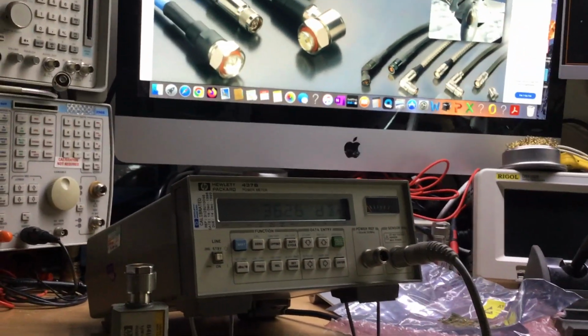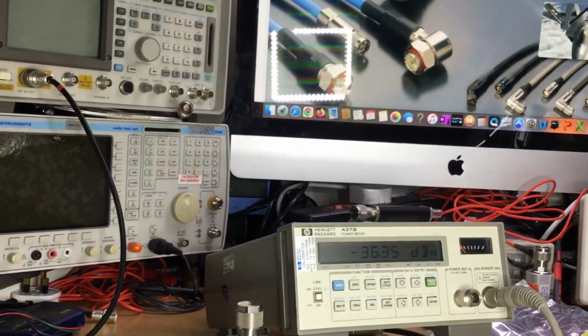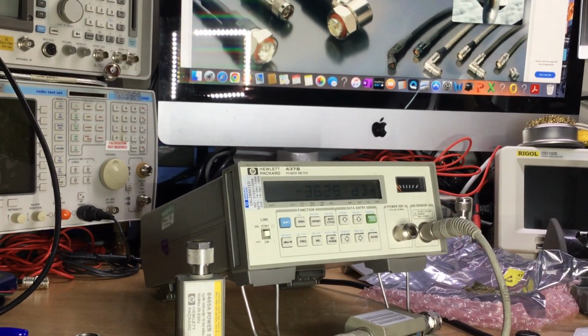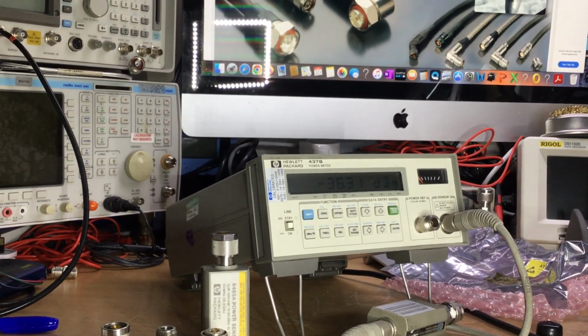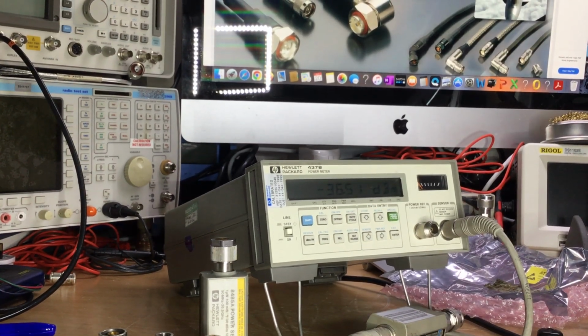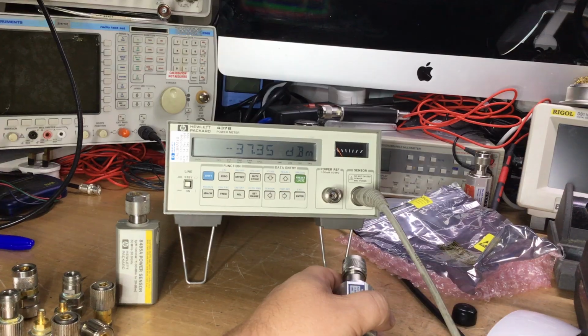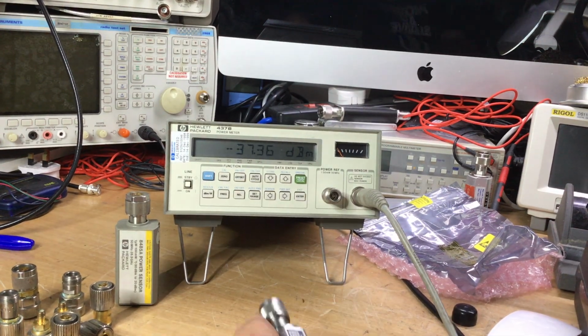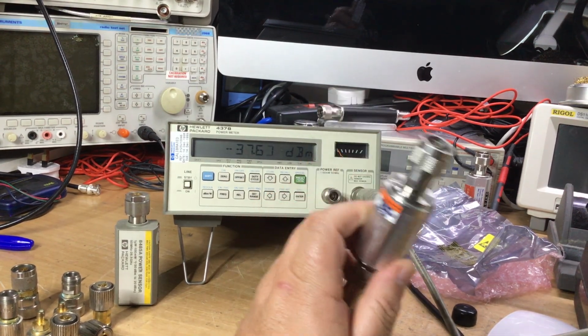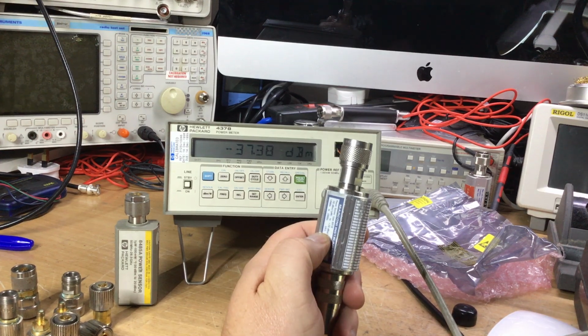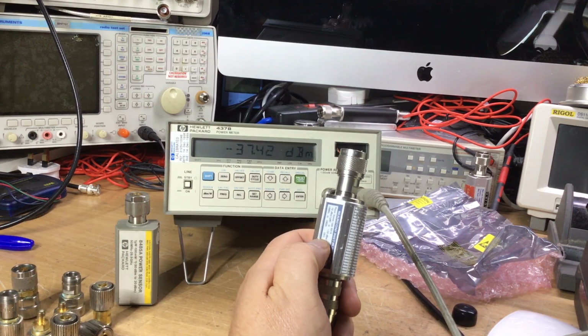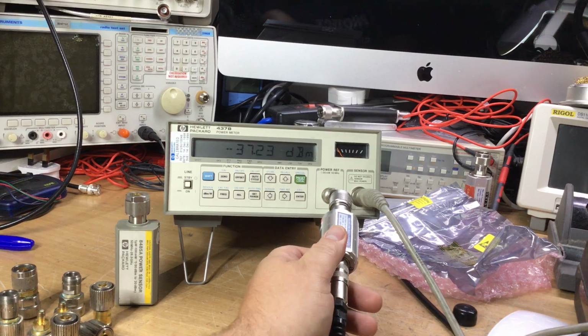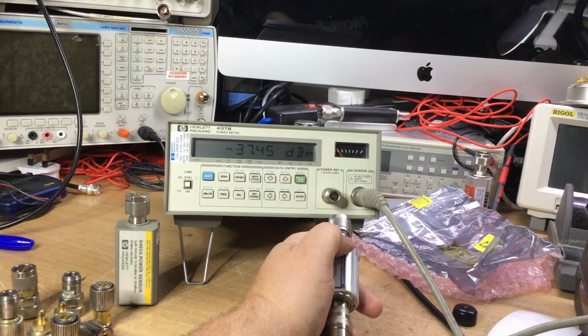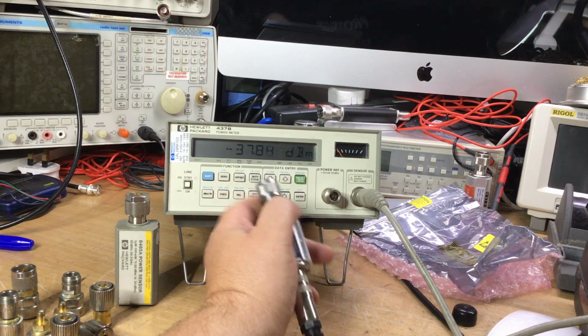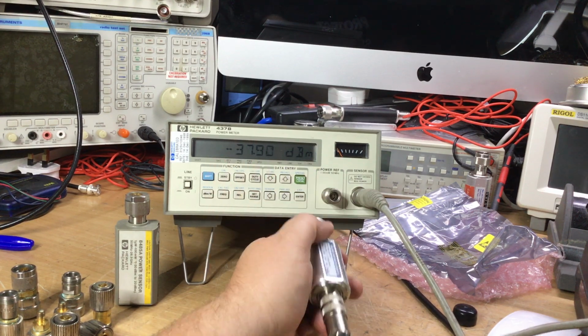So here we are. We'll come down to the sensor now in here, and we'll just reposition the camera so we can see the screen, and we'll do a measurement on this. Okay, so what we're going to do now is use the Marconi microwave sensor that we've already calibrated on the calibrated MTS, and connect it to the Type N reference power port on the HP meter so we can test the accuracy of that meter.